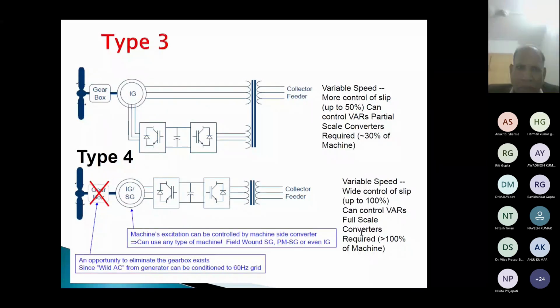Now, talking about type 3 and type 4. Type 3 is again based on the induction generator. However, type 3 is very popular as the doubly-fed induction generator. In the case of the doubly-fed induction generator, power can be fed into the grid both from the stator as well as from the rotor circuit. However, we know that the frequency in the rotor circuit is not the same 50 Hertz, so when you have to feed power into the grid, we have to bring this frequency from the rotor circuit back to 50 Hertz before that power is fed into the grid.